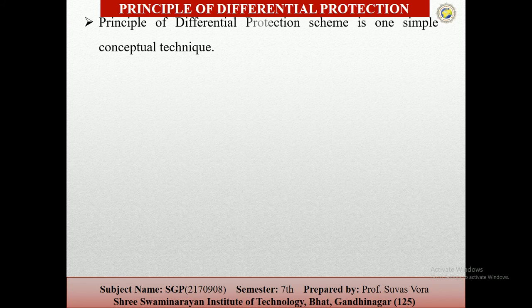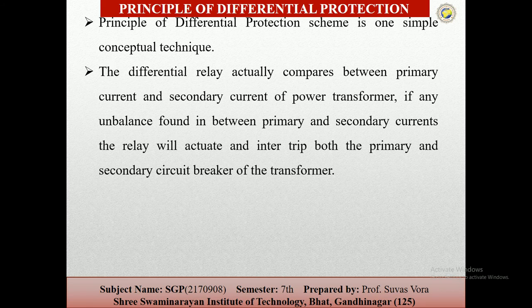The percentage differential relay consists of a restraining coil for overcoming the trouble arising out of the differences in the current ratio for the high value of external short circuit current. Basically the principle of the differential protection scheme is one of the simple concept techniques. The differential relay compares the primary current and the secondary current of the power transformer. If any unbalance is found between the primary and secondary current, the relay will interrupt both the primary and secondary circuit of the transformer.